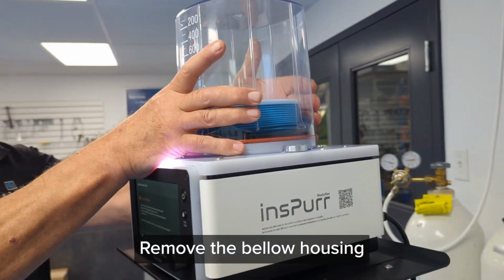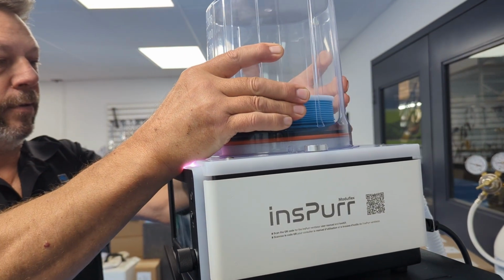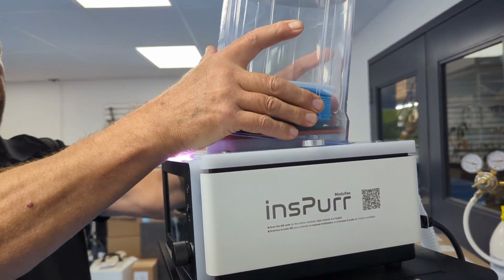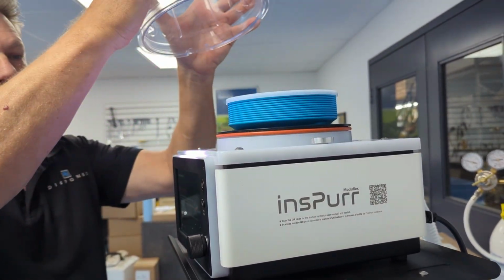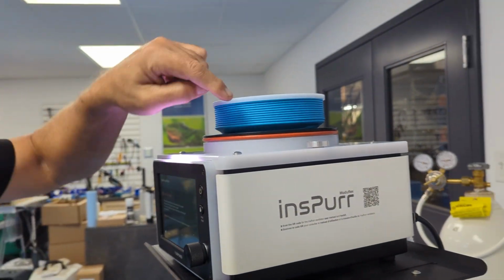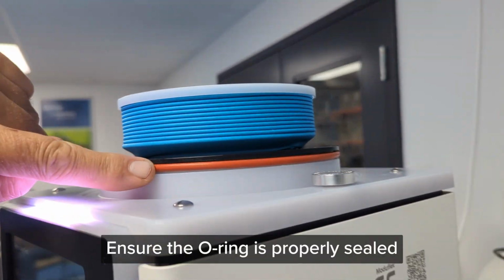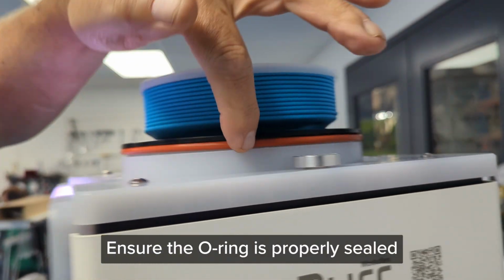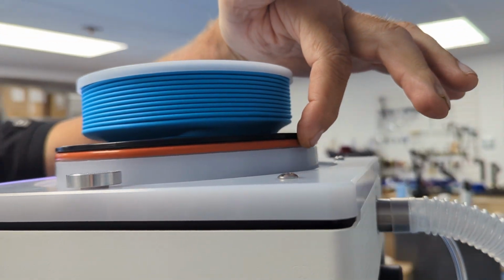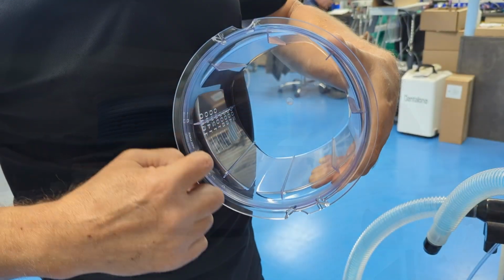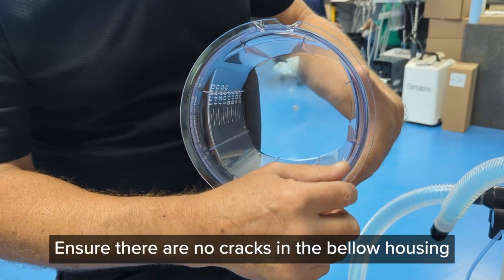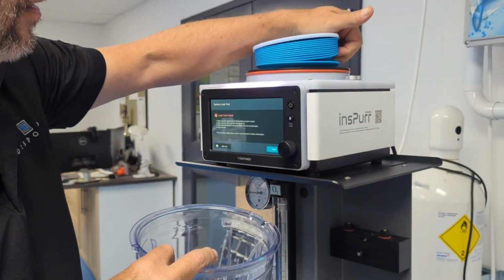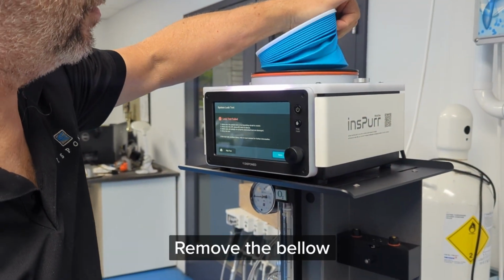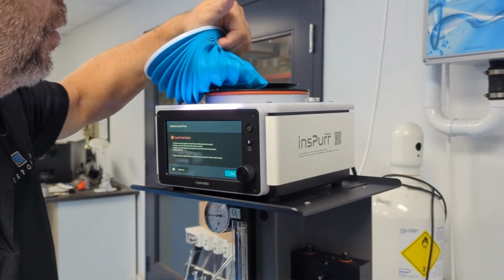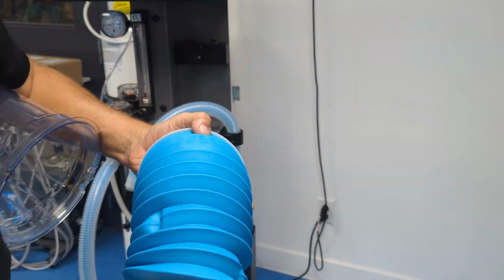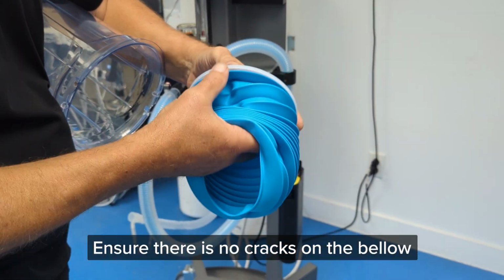Remove the bellow housing. Ensure the O-ring is properly sealed. Ensure there are no cracks in the bellow housing. Remove the bellow. Ensure there are no cracks on the bellow.